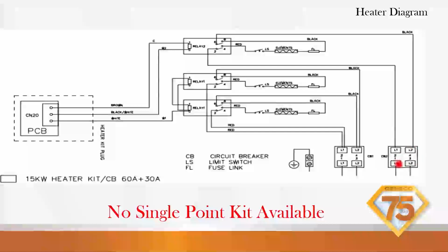labeled, because again, guys, they're just disconnecting means, it's a light switch. But you can tell because there'll be more wires coming off the load side of that circuit breaker. That's what's getting all the load. The 30 amp needs to go over here. So we swapped that up, problem fixed.